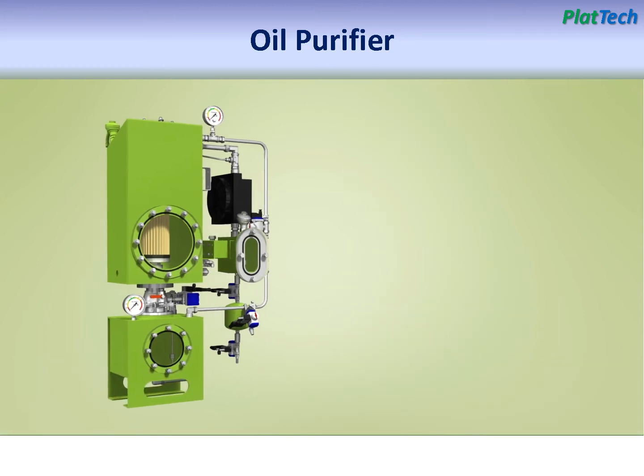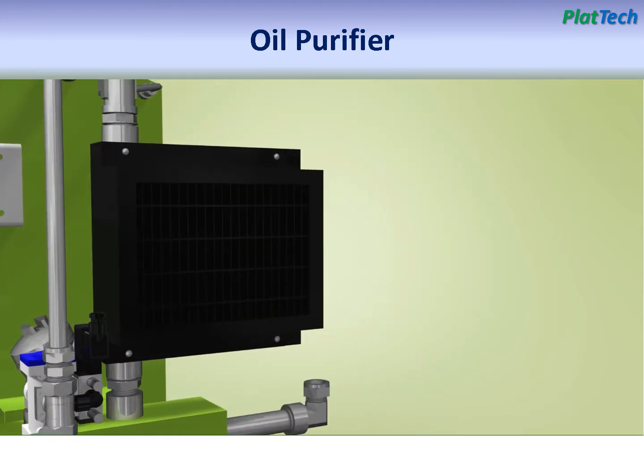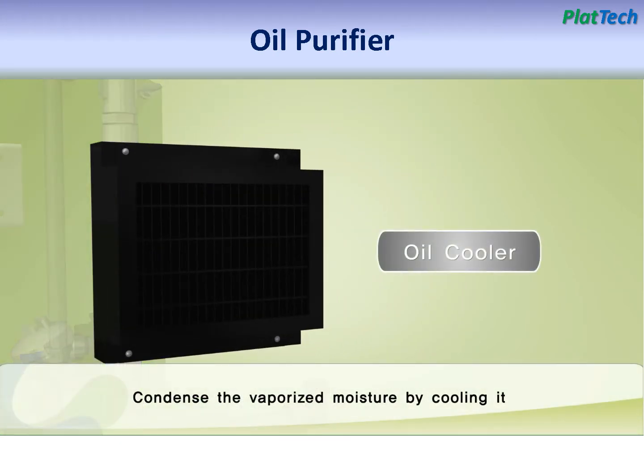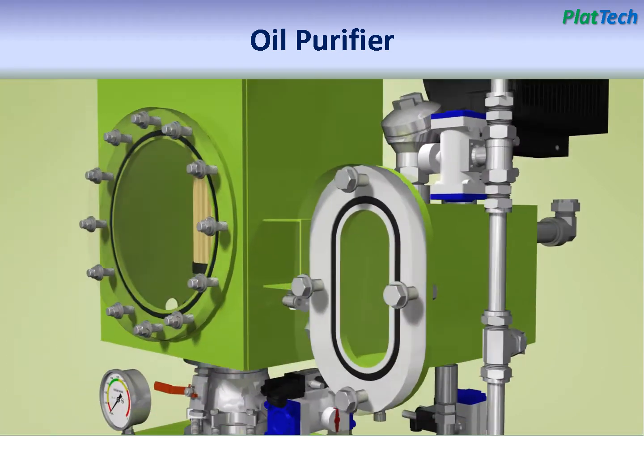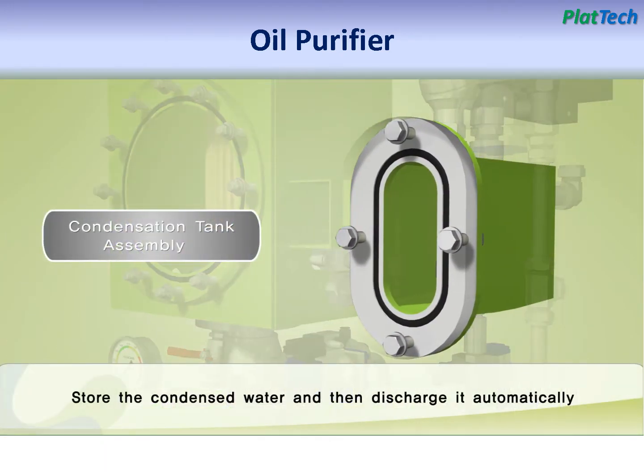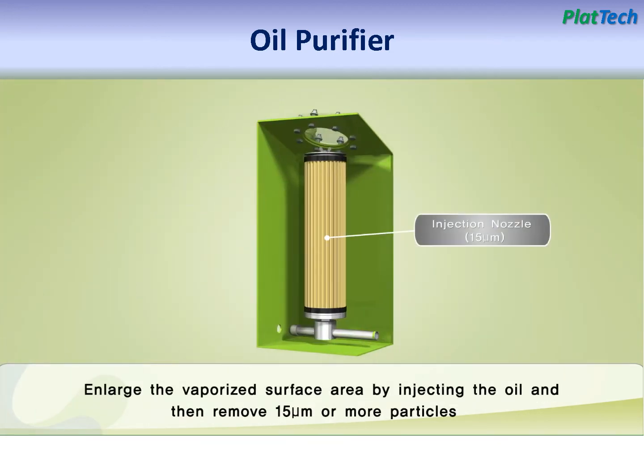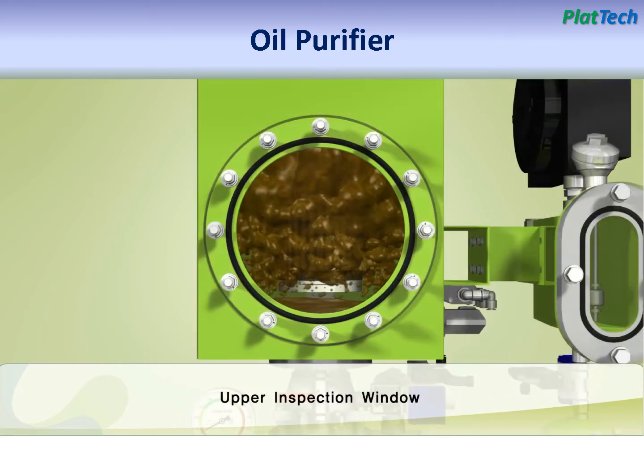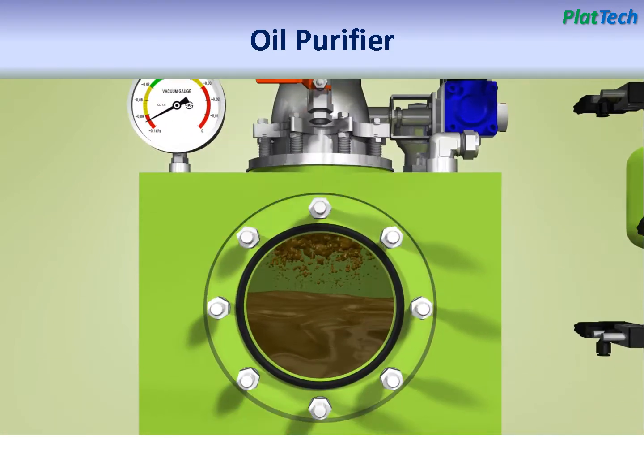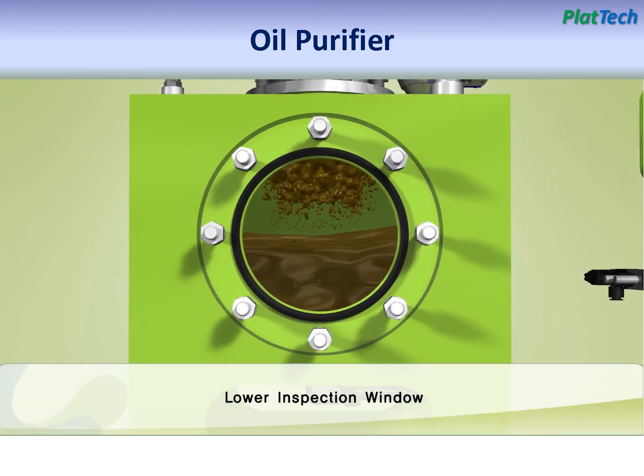An oil cooler is used to condense the vaporized moisture, and the condensate water will be discharged automatically when water level in the condensation tank is high. Injection nozzle with a 15 micrometer filtering media is used to spray oil, so dissolved water and gases can be removed more effectively. Oil condition can be monitored through sight glasses from both upper and lower vacuum chambers.